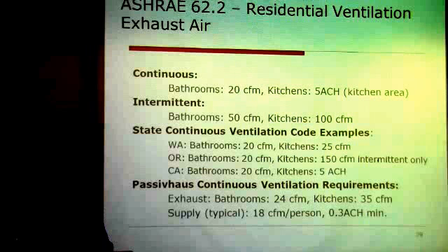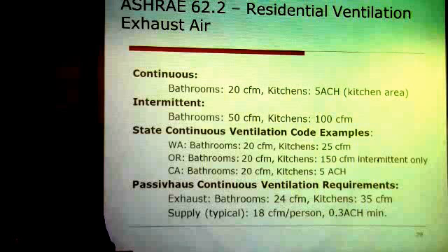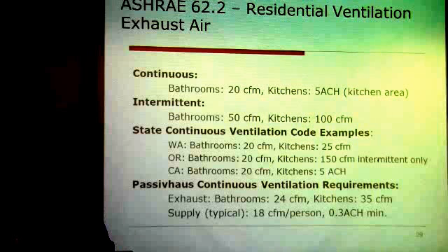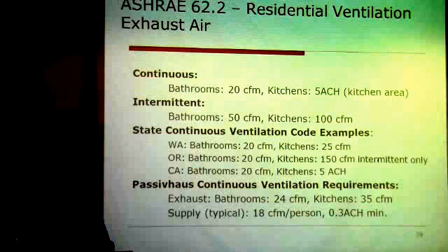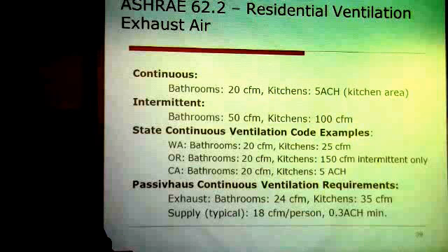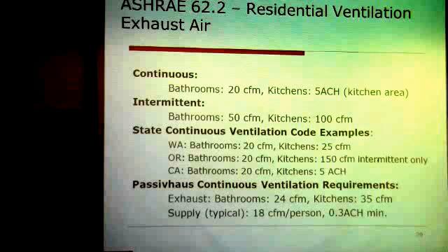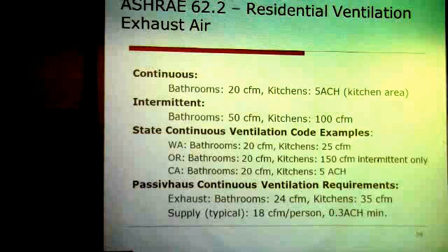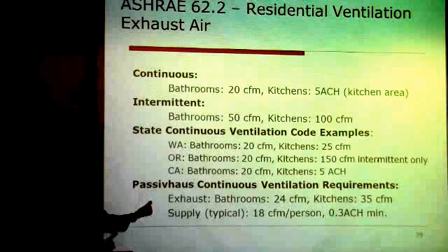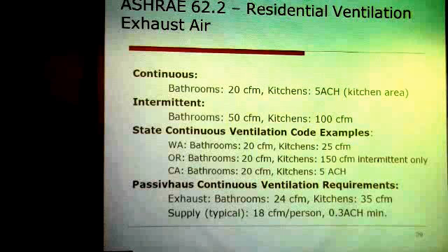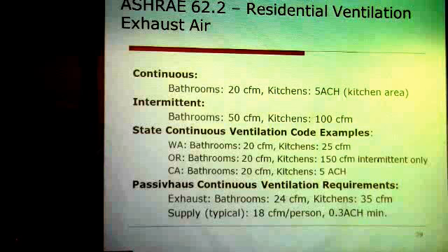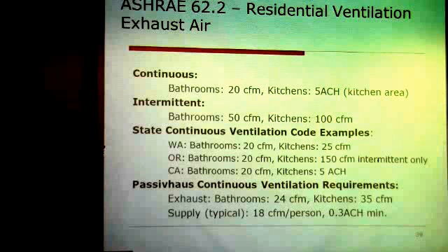Yeah, we try to just set the continuous for 0.3 air changes per hour. Okay. And then if you were to do that modification, it would go up to like 5 or 6. Yeah, unless you're with that active heat. Yeah, it would go from 0.3 plus whatever your natural is. But also if you slightly positive pressurize the house, it'll reduce the amount of infiltration too. But anyway, yeah. So you have your choice per the code.